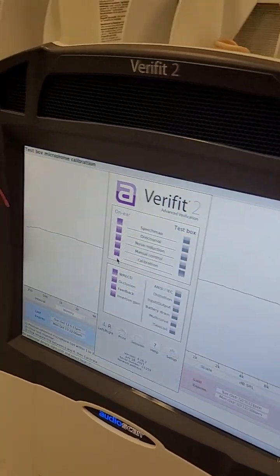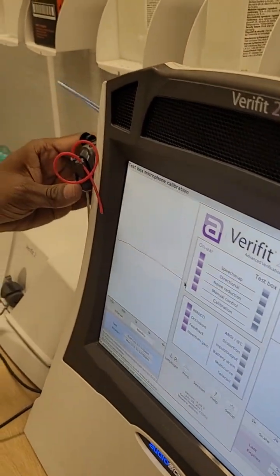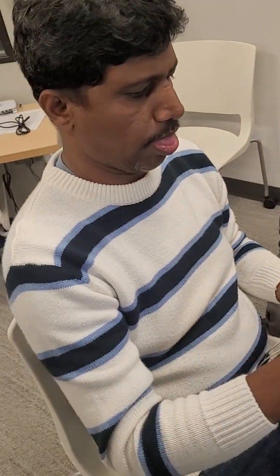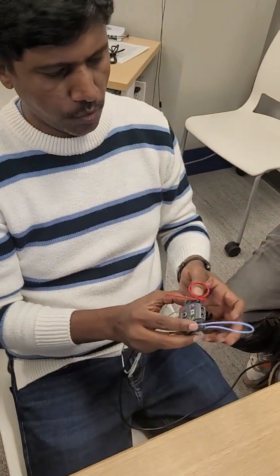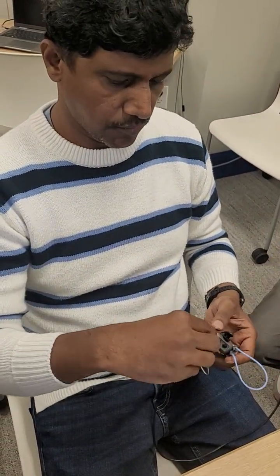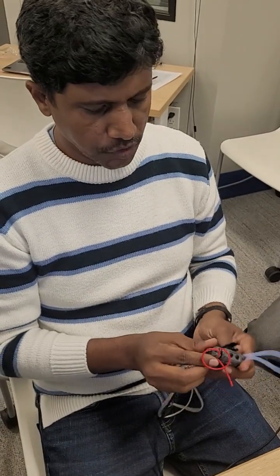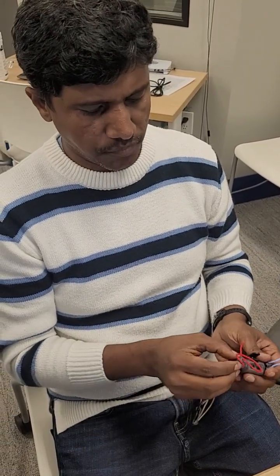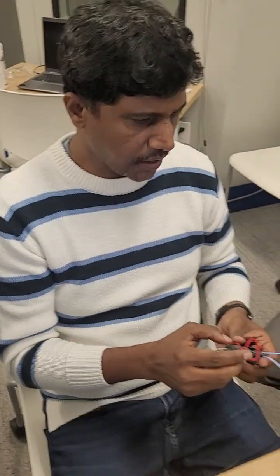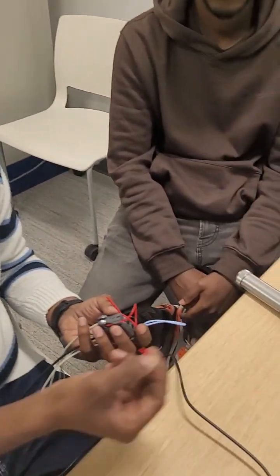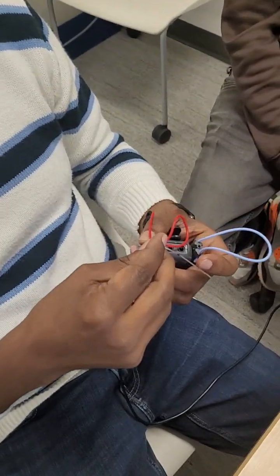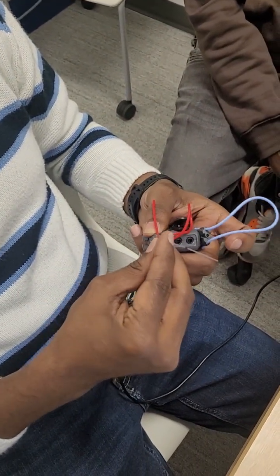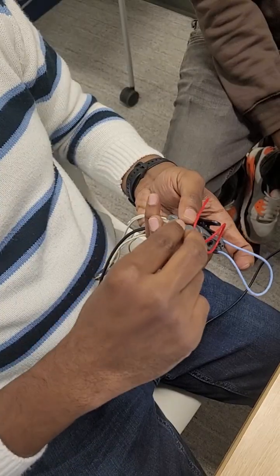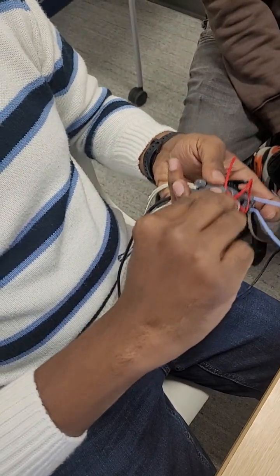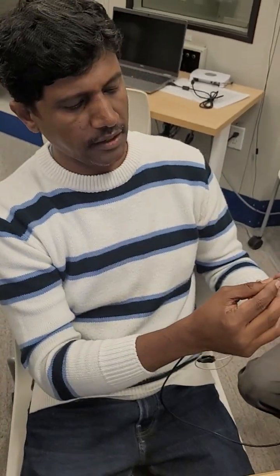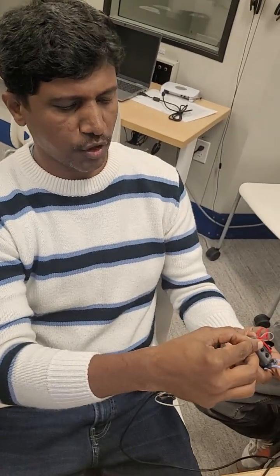So the next one is I'll be doing the calibration on the real ear. To do that, I have this real ear measurement probe module. So I have this probe dock on either side. As you can see here, the probe dock has the probe mic as well as the reference mic. I have this small probe tube which goes into the probe mic. This slide dock here I'll be putting inside there. The probe tube I'll be putting in front of the reference mic here, and it should be exactly in front of the reference mic and held through the small slot there.